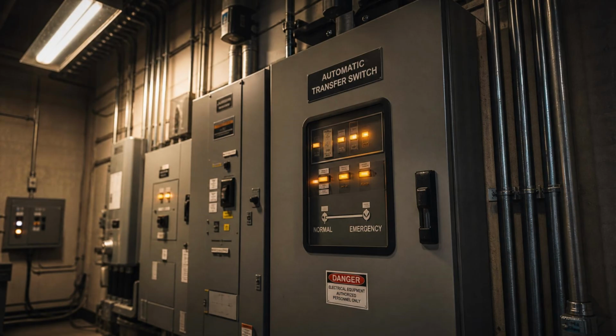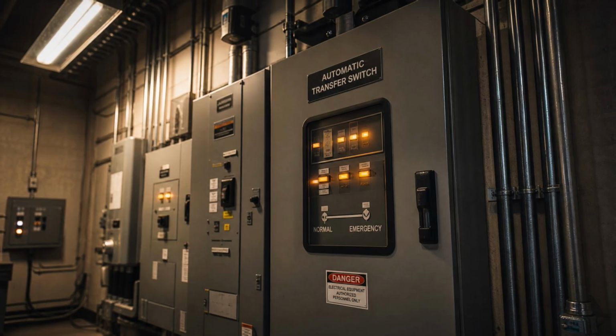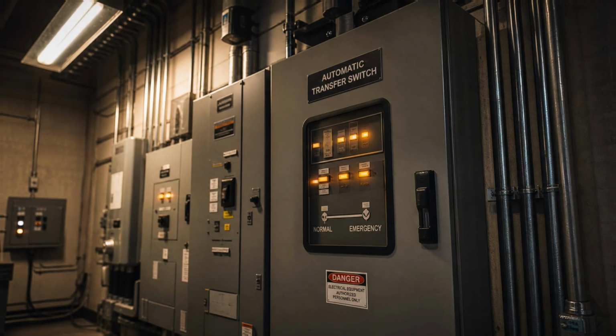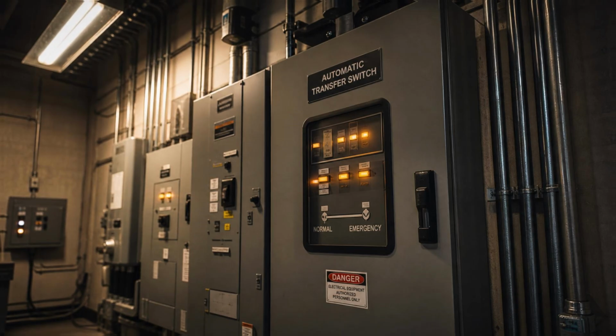This is the gap that UPS systems and battery-backed devices exist to bridge, but we will come to those in their own time. For now, we stay with the transfer switch, waiting in its cabinet, watching for the signal that the generator is ready. When that signal comes, when the emergency source has stabilized and proven itself acceptable, the transfer switch acts. Its contacts move. The connection to the failed utility source is opened. The connection to the emergency generator is closed.